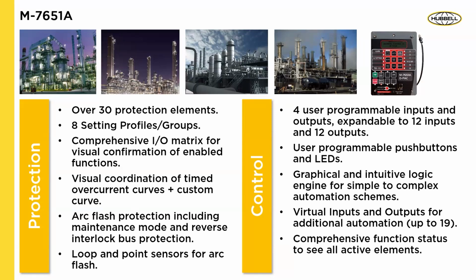Okay, so the feeder protection has 8 setting profiles and groups. It has a comprehensive I/O matrix. It has visual coordination, arc flash protection, obviously, as you saw, and a lot of programmable inputs and outputs, a graphical interface for logic development, and comprehensive function status to see the active elements. So all in all, from a protection control standpoint, what we've tried to do with this product is make it very simple, very easy to use and program, and very easy to operate, right? The ultimate goal is to spend more time doing the calculations, making sure we're getting things right, rather than spending more time programming a relay and learning how to program.